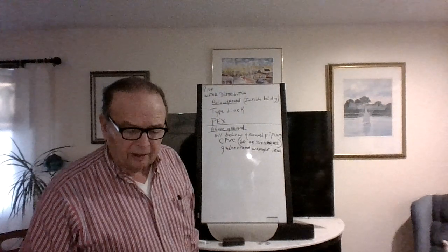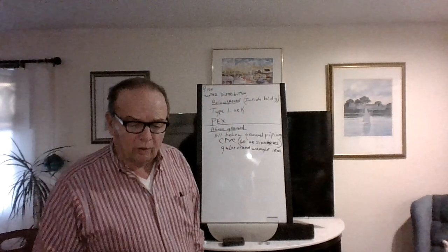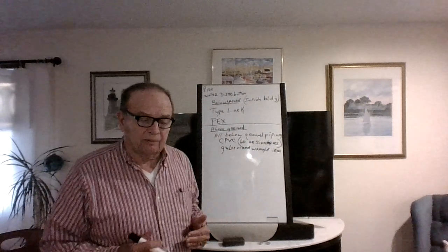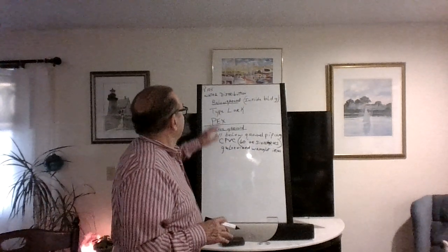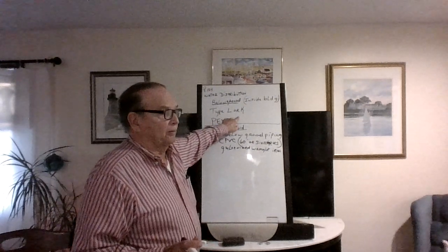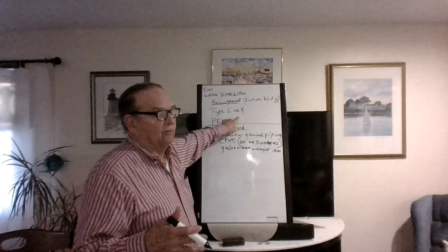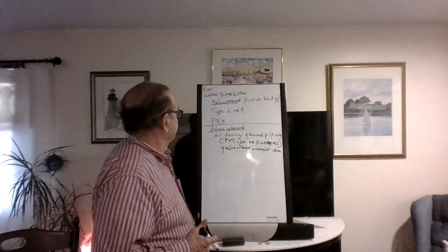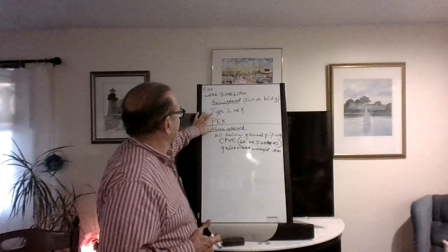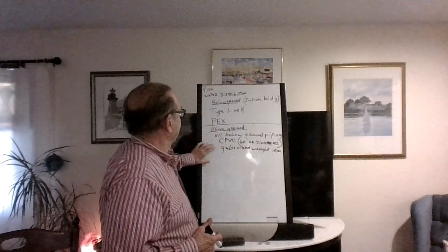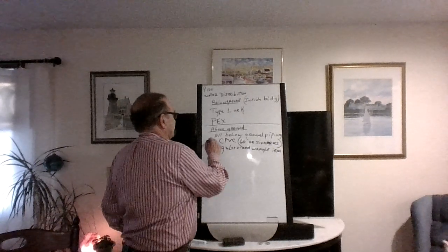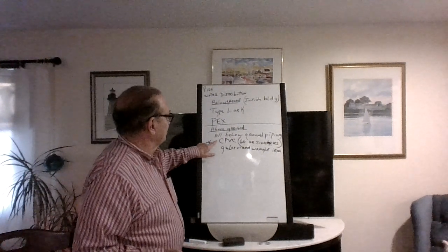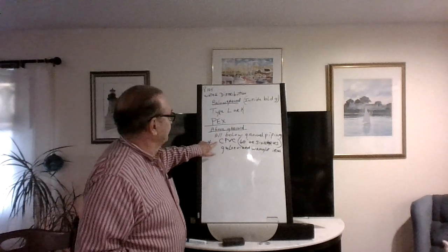So the list for above ground water pipe inside the building now. We're not outside where you might want to call it water service. This is inside the building. So this is part of the Mass Code. Type L or K. You can't use M or DWV for water pressure pipe, right? Water distribution, right? So the L or K is used below ground and above ground. The biggest difference is, this is the big one right here, CPVC. And I know a lot of you guys use CPVC for water piping. And that's fine. The stuff is durable.